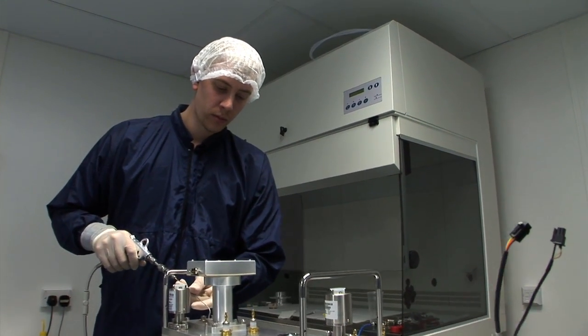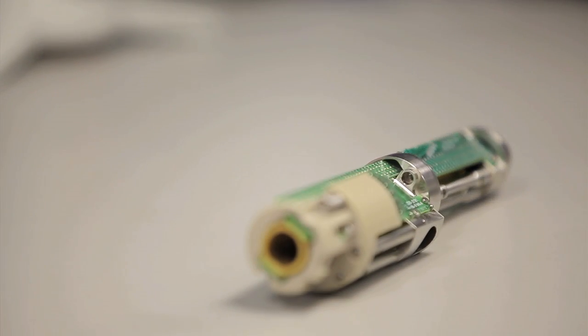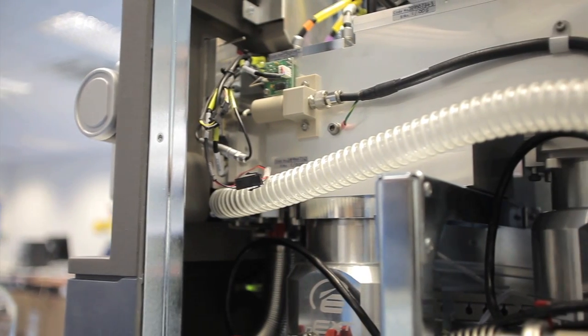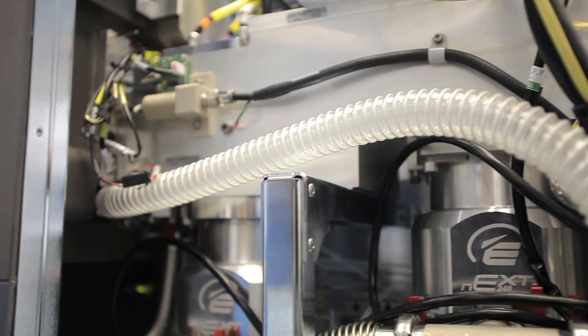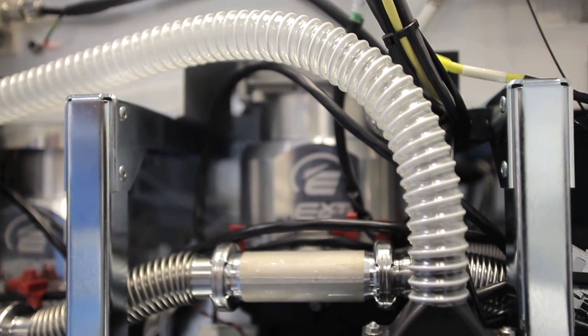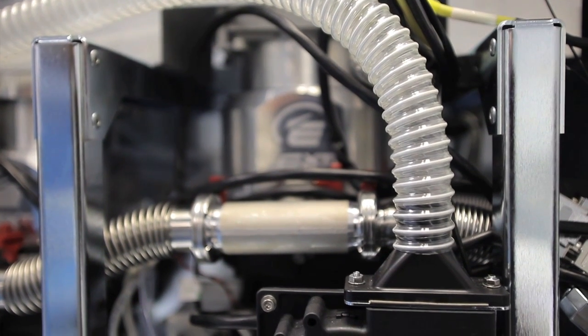The step wave ion guide uses a novel combination of travelling wave ion guides to confine, transport and focus ions through the intermediate vacuum stages of a mass spectrometer. The novel design has an off-axis element to it which allows us to maintain sensitivity and performance even for the most complex of samples.